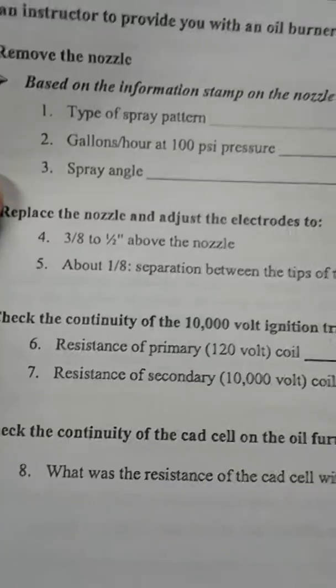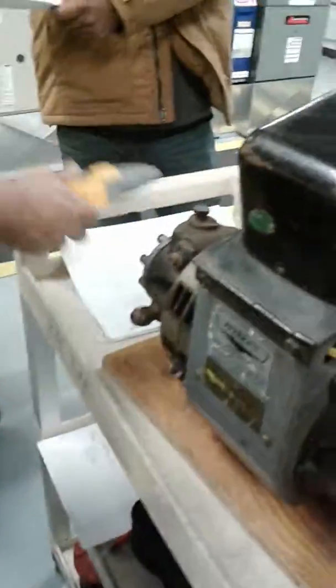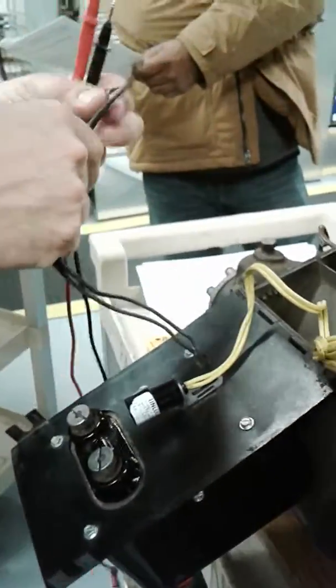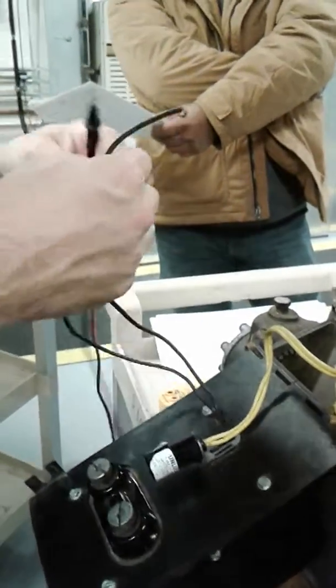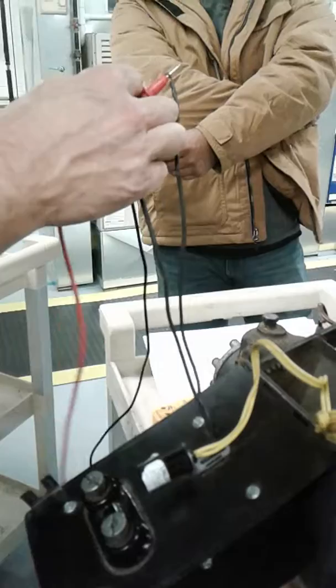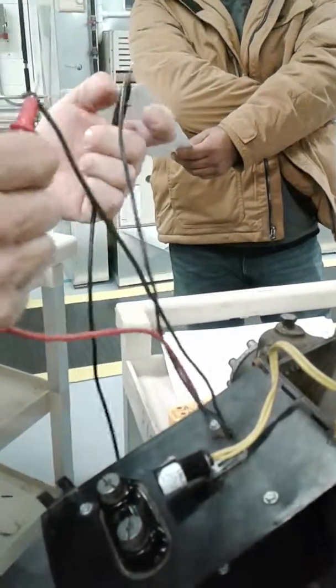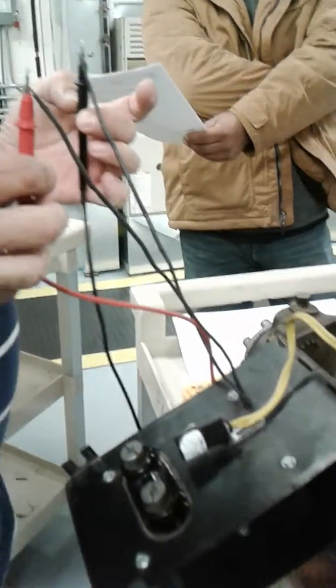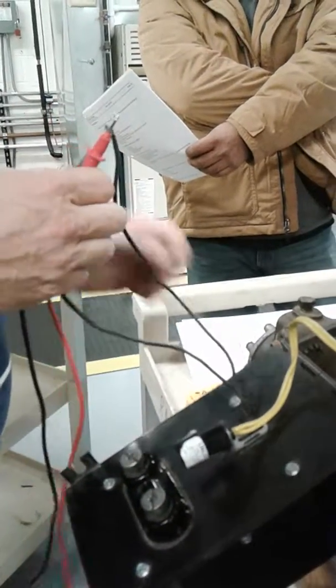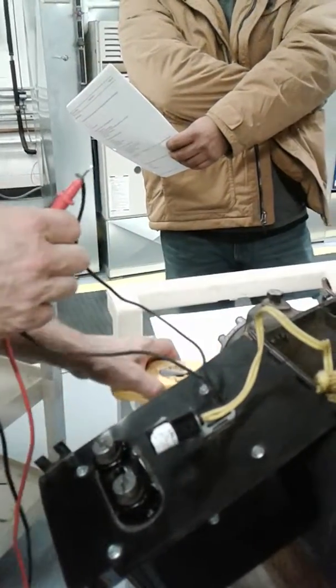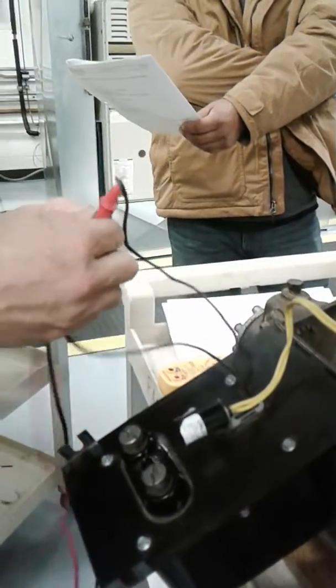Check the continuity of the 10,000-volt ignition transformer and record your results. This is what we're going to do, guys. We want to check the primary coil of the transformer. Now, I told you guys in class that this is the primary side, which is how many volts? 120. Very good. Okay? So we're going to wrap the wires around one side and then on the other side. And then we're going to measure the resistance on the primary side. And I'll write it down. Okay? All right. Next is resistance of the secondary side of the coil.